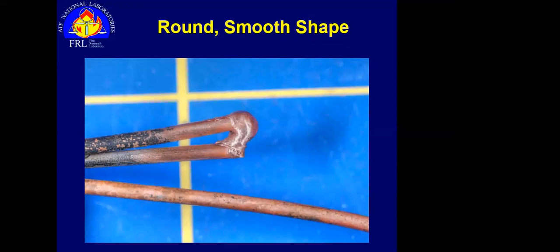Going back to that first slide, this is a non-metallic sheath cable, commonly called Romex, which is a brand name. And this was from a test burn. In this case, the hot or ungrounded conductor is on the top, the ground is in the middle, and the neutral is on the bottom. So how is it that fire impingement is going to be so localized and focused that it's going to melt 2 out of the 3 conductors and leave the third conductor, a millimeter away, completely undamaged? Again, it's repeating the same question. There's no way that fire is going to be this precise.